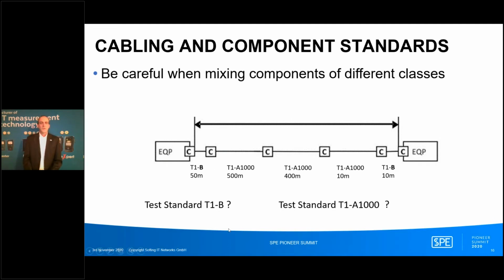So how do you test that? Can I test that to T1B limits or T1A1000 limits? In cabling tests, the important thing is that the lowest performing piece, from an RF measurement point of view, is the limiting factor. The T1A1000 is a 0.1 to 20 megahertz link, and this other one is a 0.1 to 600 megahertz link. So from an RF point of view, the T1A is the lower performing thing here. So what you actually need to do is test this particular example to T1A1000 limits, as an example. So just be cautious with that.